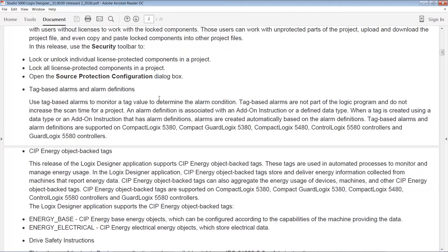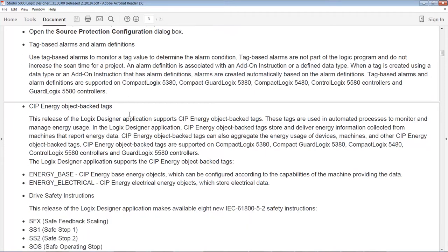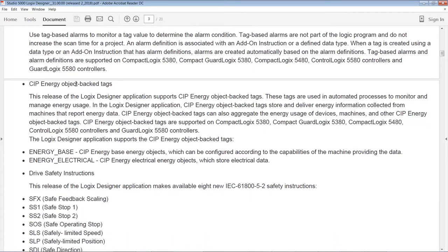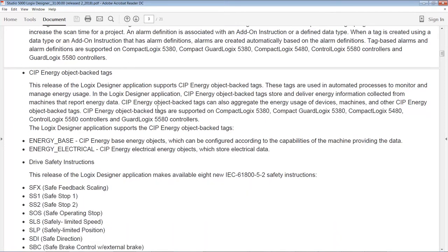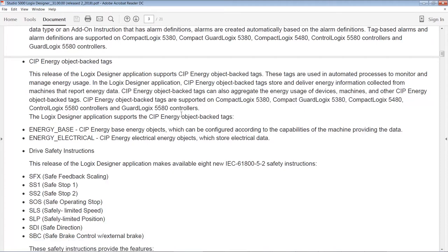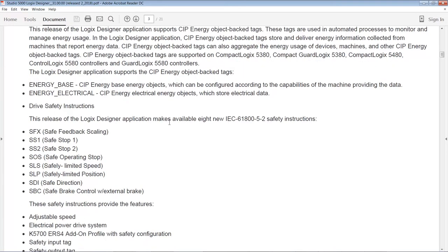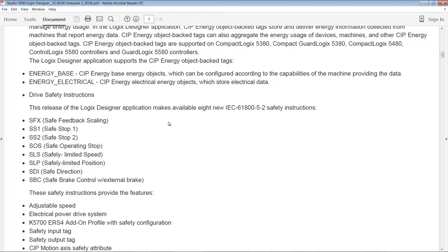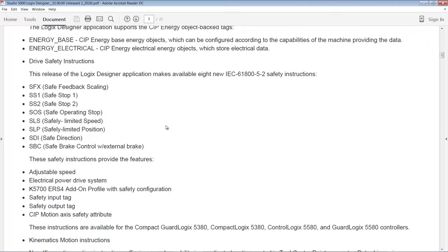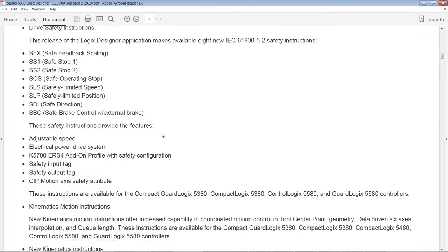They also added some CIP Energy object-backed tags. If you're doing anything with energy and you're using software that supports this new CIP Energy feature, then that's cool. It does a lot of the stuff in the back end for you. Again, only on the 5x80 controllers. A bunch of new safety instructions for drives, including things like safe feedback scaling, safe stop one and two, safe operating stop, safely limited speed, safely limited position, safe direction, and safe brake control with external brake. So those are all pretty cool new features to have if you're doing any integrated safety with drives.